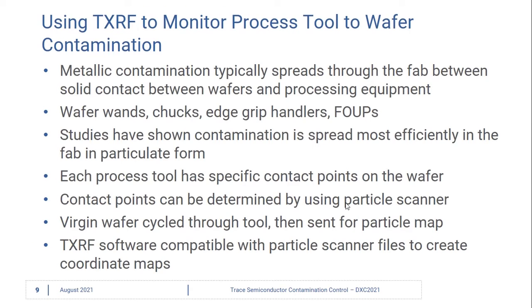Now we'll talk about how we use TXRF to monitor process tool-to-wafer contamination. Metallic contamination typically spreads through the fab between the solid contact points of the processing equipment and the wafer itself.